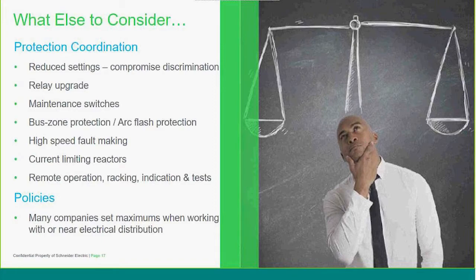One of the things we can also think about, as we talked about, is remote operation and racking. There are lots of technologies around now for operating and maintaining this equipment, whether it's retrofitting new equipment into old switchboards or replacing old switchboards with new. There are a number of control functions available now to reduce the risk. That's the first form of mitigation: take the risk away by taking the personnel away from that level of incident energy. That really is the first stance. From then onwards, you've got a variety of different options to try and minimize the risk.